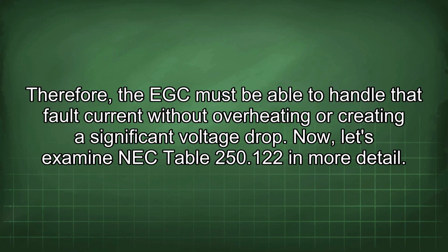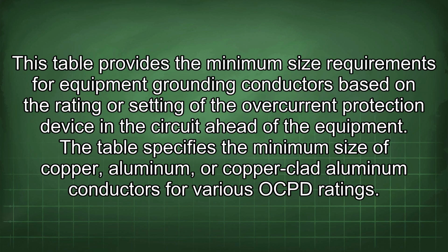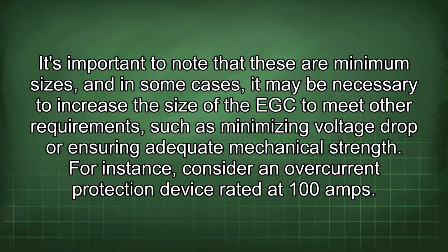250.122 in more detail. This table provides the minimum size requirements for equipment grounding conductors based on the rating or setting of the overcurrent protection device in the circuit ahead of the equipment. The table specifies the minimum size of copper, aluminum, or copper-clad aluminum conductors for various OCPD ratings. It's important to note that these are minimum sizes, and in some cases, it may be necessary to increase the size of the EGC to meet other requirements, such as minimizing voltage drop or ensuring adequate mechanical strength.